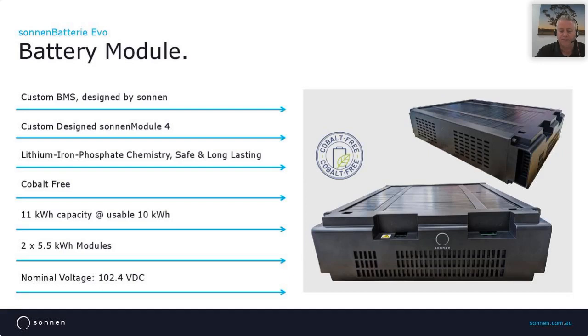Custom Sonnen Module 4 with custom BMS designed by our Sonnen R&D team in Germany. We continue the Sonnen tradition of using safe and long-lasting LFP chemistry, which is cobalt-free. Cobalt is a toxic heavy metal that can be mined unethically and also reduces the recyclability of battery cells. Each battery module has a capacity of 5.5 kilowatt hours, giving the sonnenBatterie Evo a usable capacity of 10 kilowatt hours. Each module has a nominal voltage of 102.4 VDC, paired in series, giving the system a total nominal voltage of 204.8 VDC.